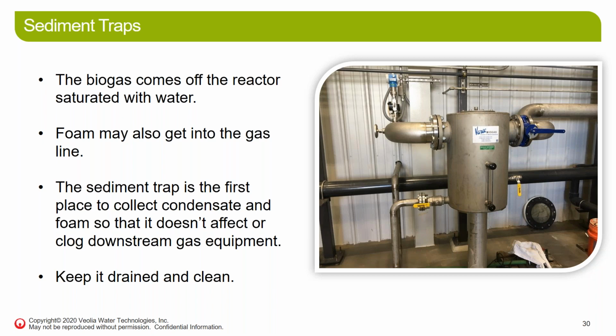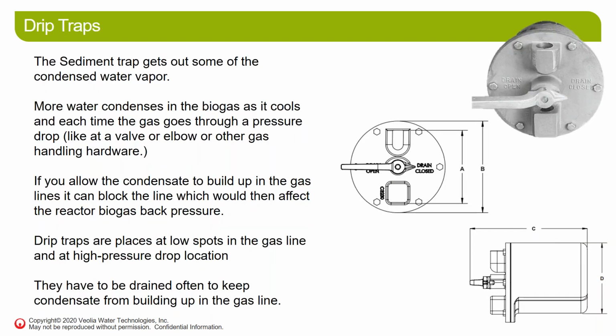Biogas is saturated with water. You may also get foam in the system. So that sediment trap collects the condensate and foam so it doesn't impact the downstream equipment or block the lines. So just always make sure that it is drained and clean. When you're down for maintenance, open it up, clean it out, things like that.